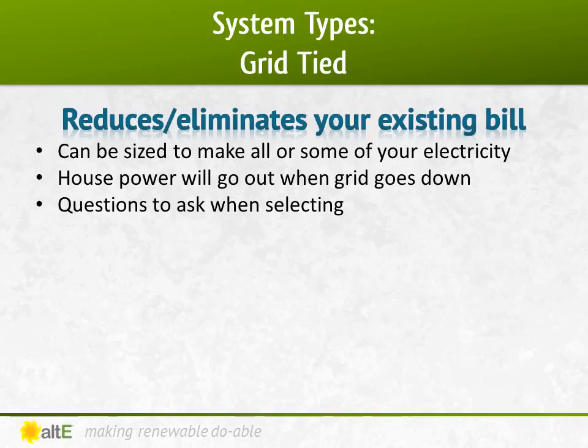The downside to a straight grid-tied system is that if the grid goes out, so will your house's power. Even if it's a beautiful sunny day, your system is required by law to turn off. This is because the inverter is connected directly to the grid. If the grid is out, the linemen will be out there working on restoring power — they are not expecting there to be any power on the lines. If your system was still up, you run the risk of electrocuting them.